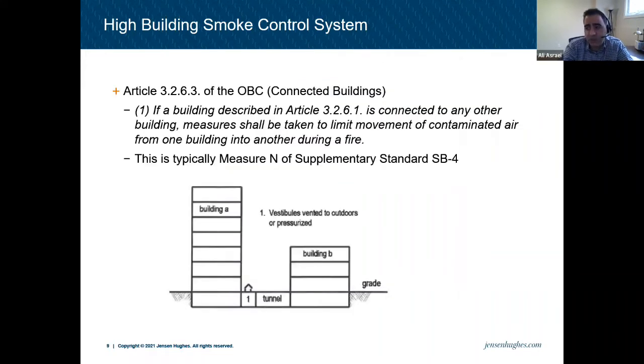That was 3.2.6.2, and 3.2.6.3 is talking about connected buildings. If you have a high-rise building connected to an adjacent building, either a high-rise or other buildings, the building code is asking for measures again. This is typically known as Measure N, a measure from SB-4. Again, there is a vestibule. Here, as you see, there's a connection between the two buildings. This vestibule is either pressurized or naturally ventilated to outside, so it prevents smoke from traveling from one building to another. That's another measure that we're taking.